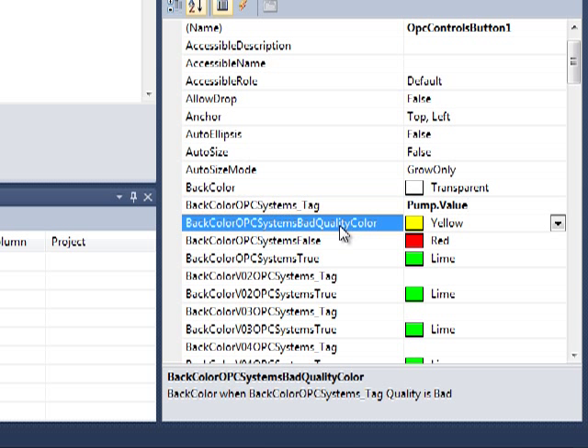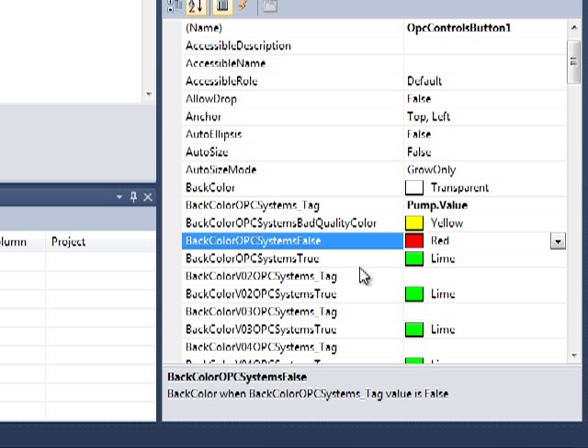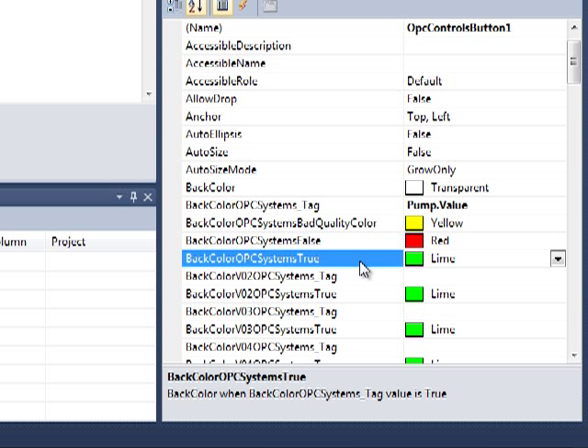We now have our tag in our back color OPC Systems tag property. Notice that the back color OPC Systems bad quality color is set to yellow, false is set to red, and true is set to green. We're going to leave these as their defaults, but you can select any color that you wish.